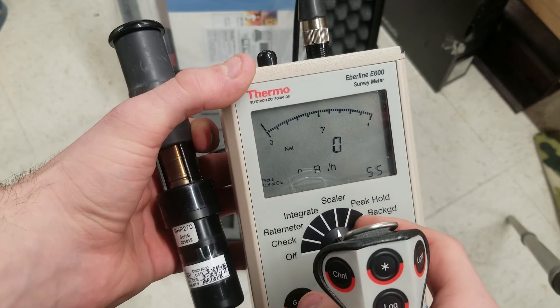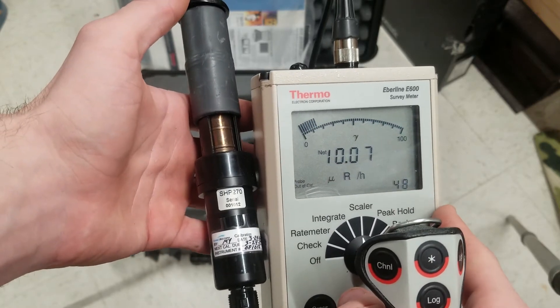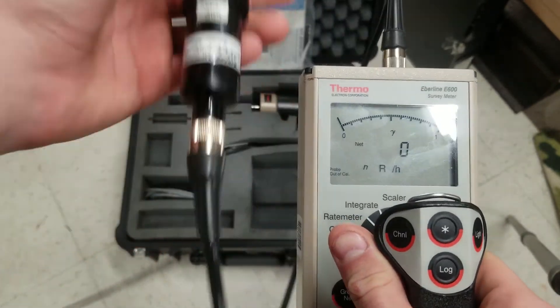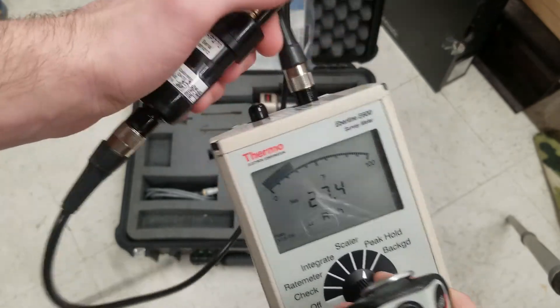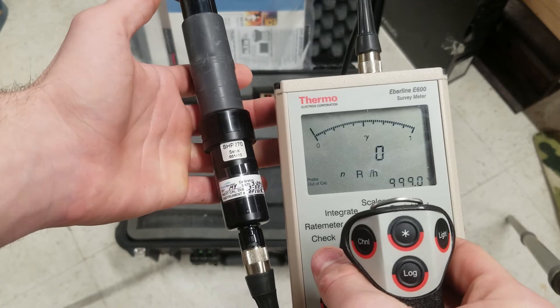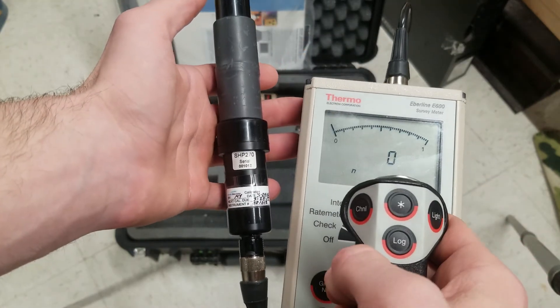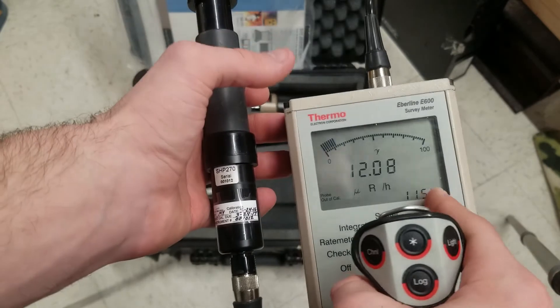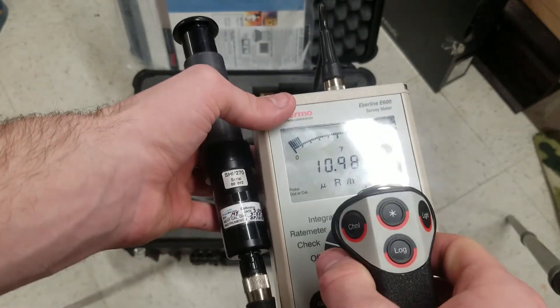As soon as you enter scaler it will immediately start counting and give you a countdown — in this case these are set up for one-minute times, then your approximate count after one minute. Peak hold will hold the maximum reading you got off the probe regardless of what readings you're getting. Background will measure what the background is — it does a ridiculously long time usually when you start it via star, and it shows percent until completion. I haven't let one run long enough to complete a full background scan.